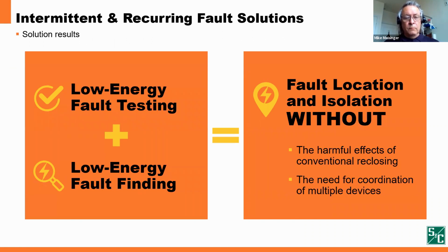So what we showed you here is how low energy fault testing and low energy fault finding can be combined with a technique we call TCC shifting to ensure that faults are isolated without the harmful effects of conventional reclosing, and the ability to intentionally miscoordinate devices to improve feeder segmentation.